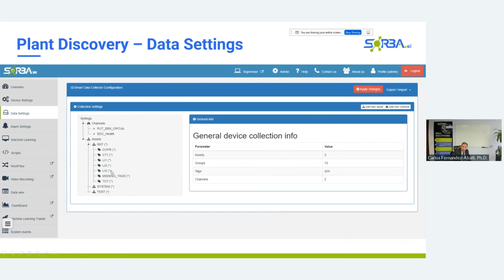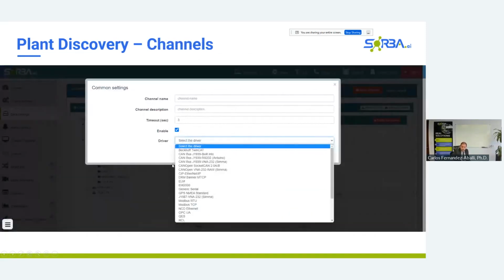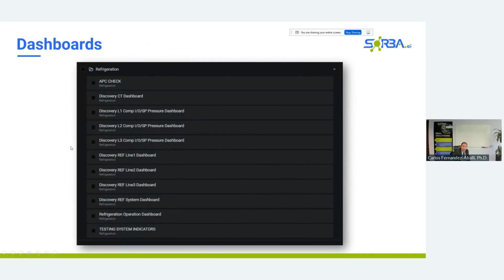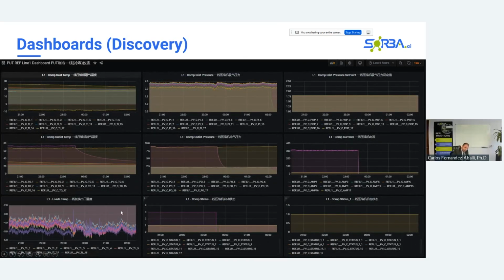And then you have to calculate your COP, your COPC, your enthalpies across the system in order to linearize the performance of your system, to help the artificial intelligence use the metric of optimization, the heuristic that we had seen before, and find that optimal behavior. Once you program your data settings, you can connect each variable directly to your PLC or to the OPC UA server, through Modbus TCP. There are over 20 different industrial drivers already set up in the SDC to be programmed through your channels. And you have a group of dashboards already created, which are easily programmable to see all your process variables in real time.